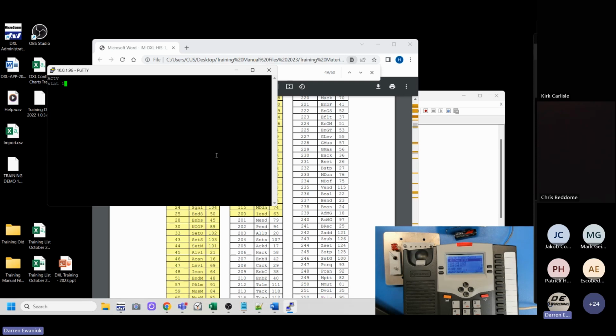So I can resend the stat command, and the system will send you all the activity for that master as if that happened right now. Bang, bang, bang, bang, bang. There's all my call requests. Now, if your touchscreen system was active, you want to look at your screens and make sure you got all the call-ins that you pressed. So this is a very good way of determining.